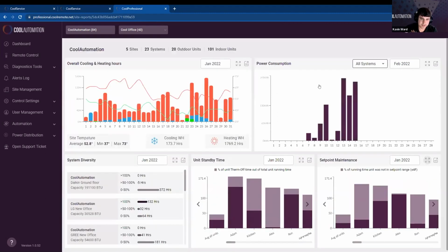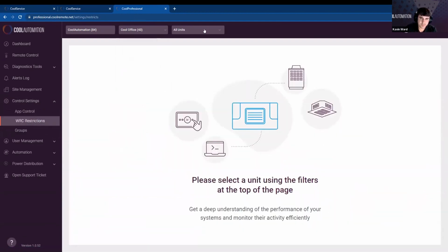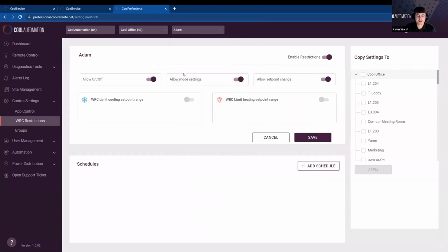So let me show you how to leverage the control of your space using some wired control restrictions. In order to gain better control of your space, our service app also gives you the capability of limiting the cooling and heating set points from the wired controller. In your hotel, for example, in the corridors, if we just want those set points to always be within 72 and 78 degrees Fahrenheit, 72 to 80. And in heating, 90 is unrealistic, so we'll leave that as a 78-degree upper limit.